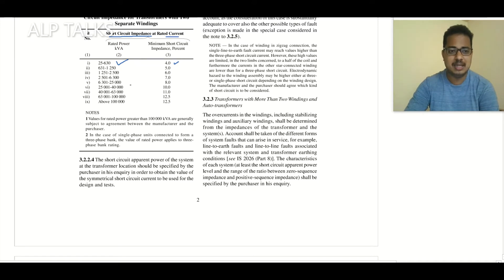From 2500 to 6300 kVA it is 7%, up to 25 MVA it is 8%, up to 40 MVA it is 10%, up to 63 MVA it is 11%, up to 100 MVA it is 12.5%. Above that, it is generally based on agreement between the customer and manufacturer, also depending on fault current and voltage regulation requirements.